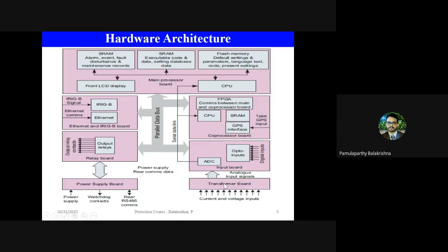So these are nothing but miniature CTs and PTs, which take 1 amp or 5 ampere inputs from the CT, or 110 volts input from the VT, whose primary is connected to the live power system machines or the power system lines. Okay. So once the CTs and PTs come, the next step is to digitize the data after doing sampling and holding, and the digital data is further sent to the processors for further action.